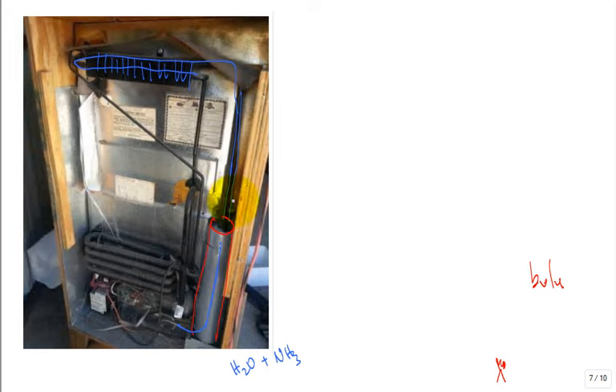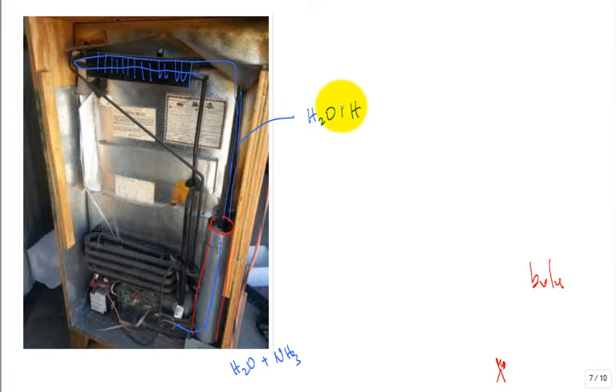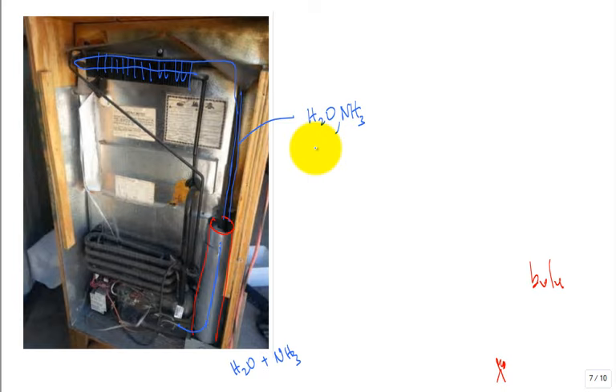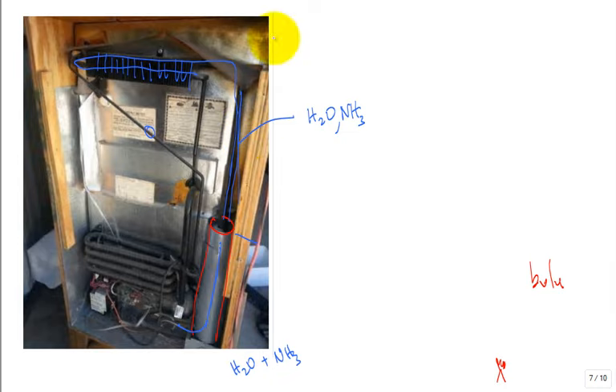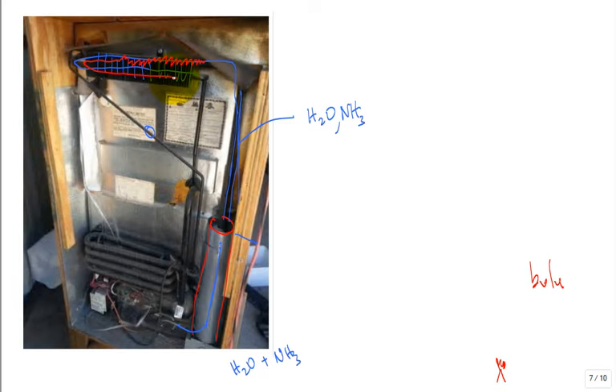What's going on here? It's like our generator. It's trying to get a vapor stream of ammonia to go up. It's hot, so the ammonia and water want to separate and the ammonia goes out. When it gets up here into the finned condenser section, it's going to condense. When it condenses, you're going to have liquid ammonia.